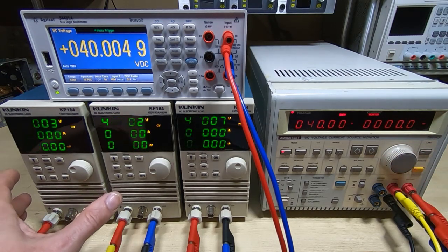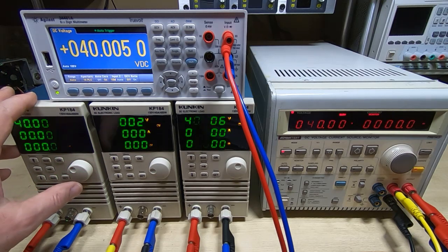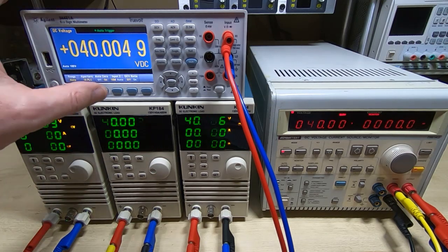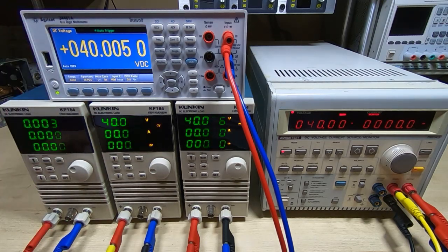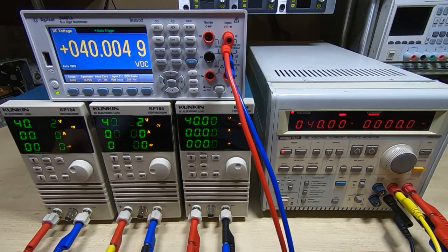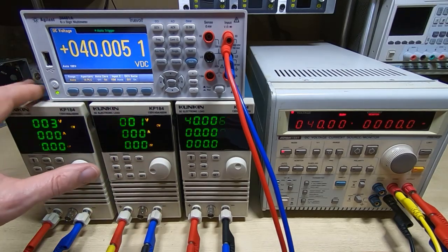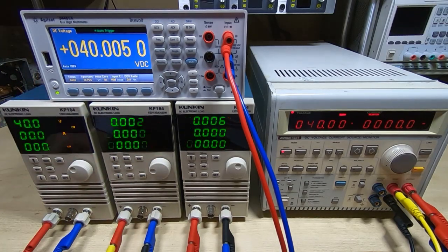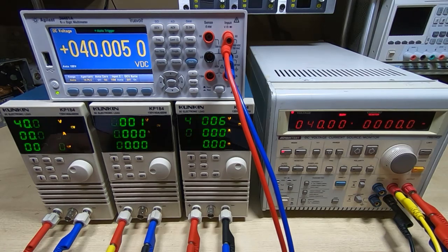I'll do the same thing with the current, get the current all reading the same and in line with the reference. But as you can see we're now quite close. And it does get to show that these are capable of reading quite accurately if they're set up properly.